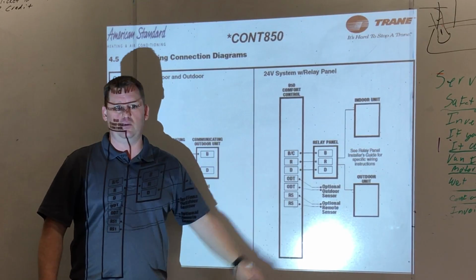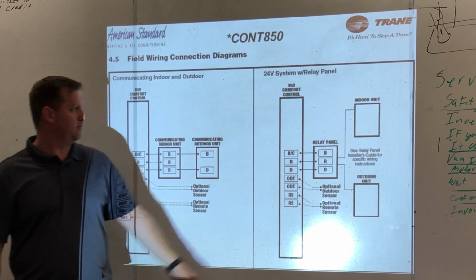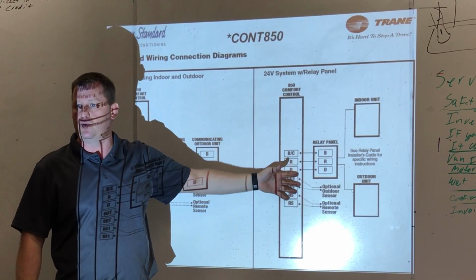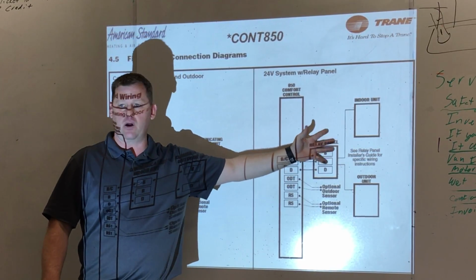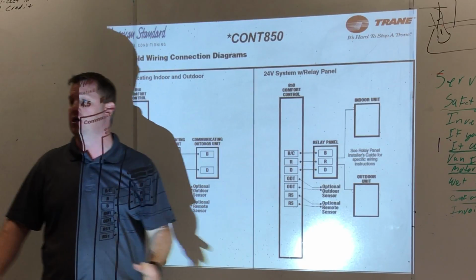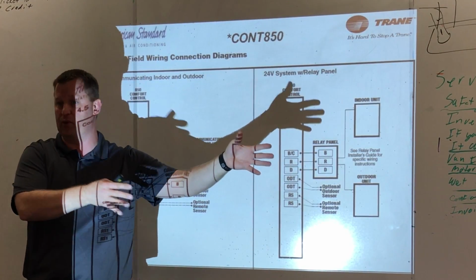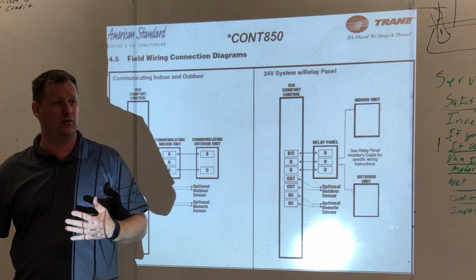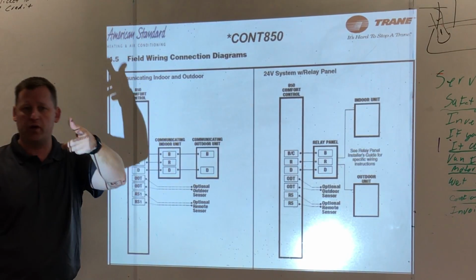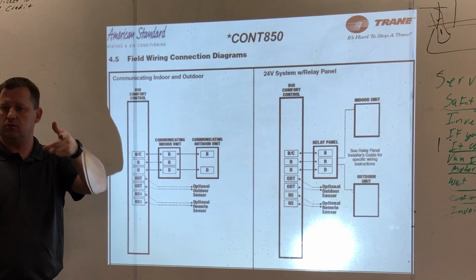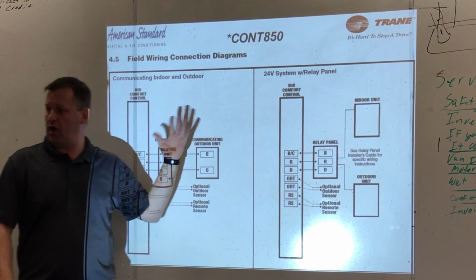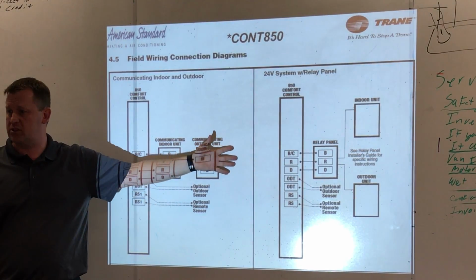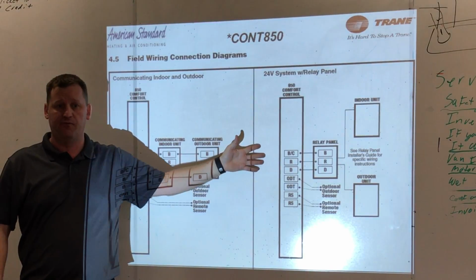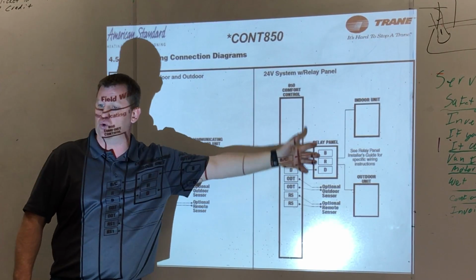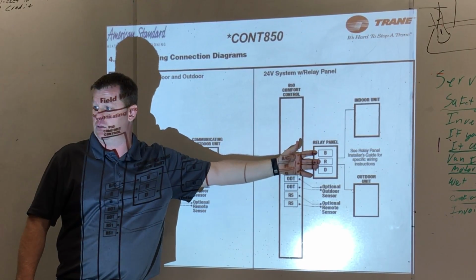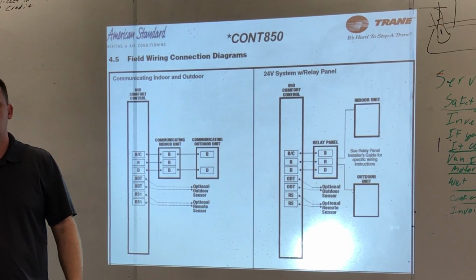Well, you know, the $50 or $20, whatever the difference between the 824 and another $100, $150 for the relay panel, whatever that is, can end up being a whole lot cheaper than a couple hours labor for a couple guys, right? Ken's gonna make that decision for you, right? Okay. But if you got an 824 and you're gonna have to repull stat wires, you probably ought to be talking with Ken. Find out if he really wants you to repull wires or if we're gonna go with an 850 with the relay panel. If it's a tight crawl space, tight attic, we're pulling wire.